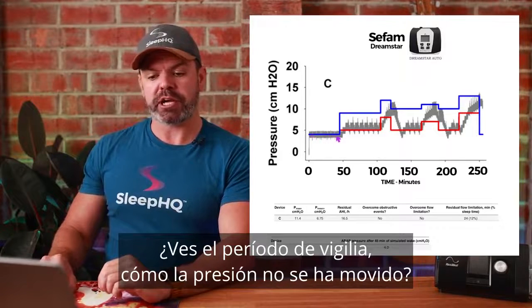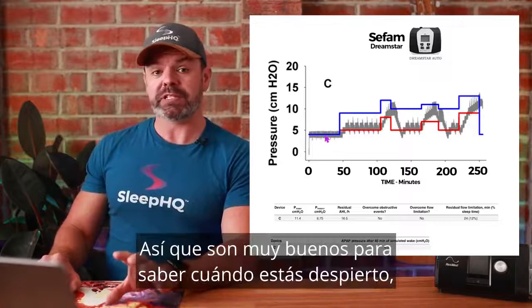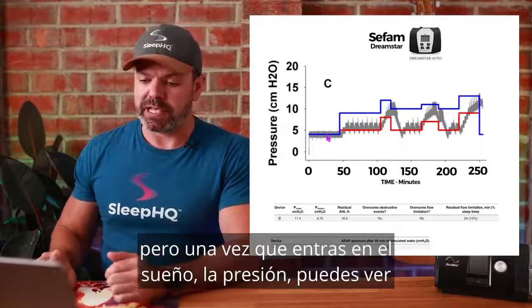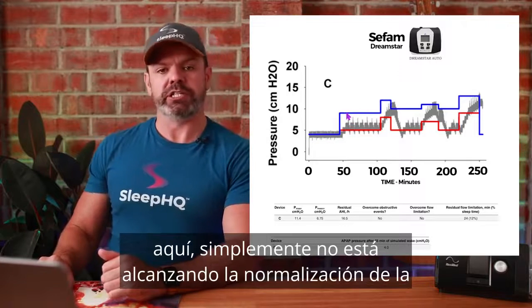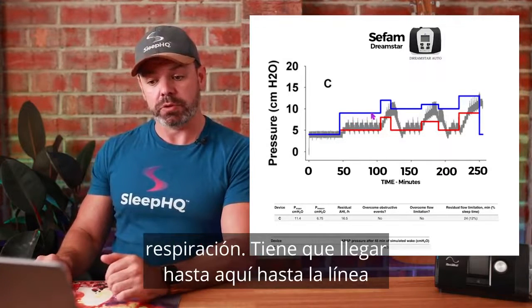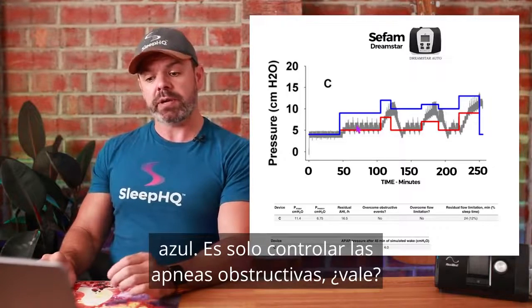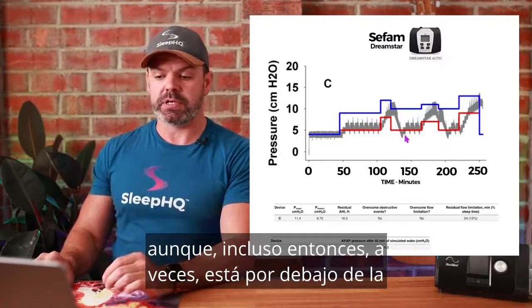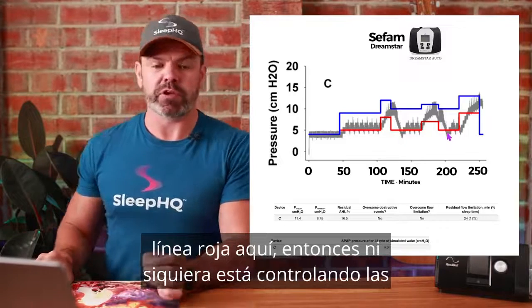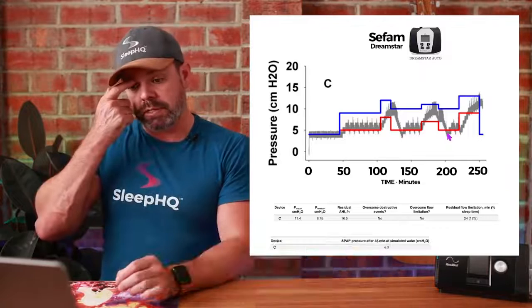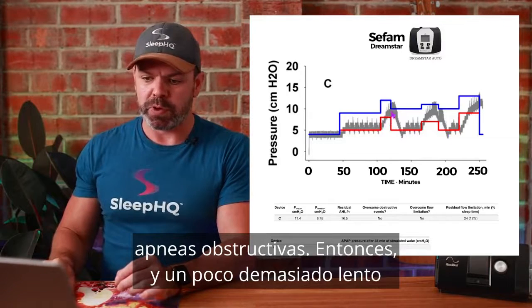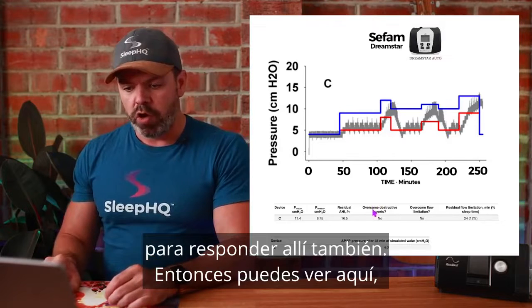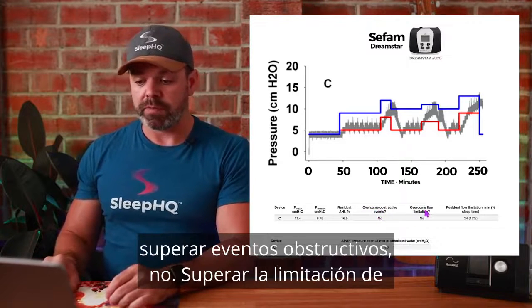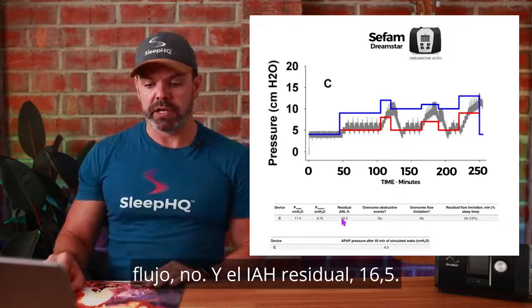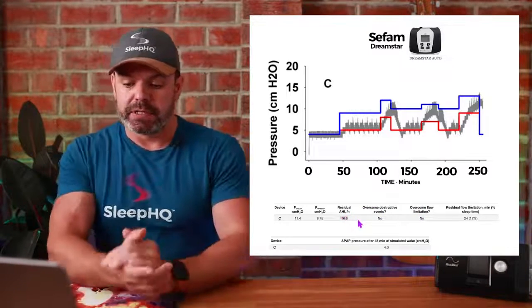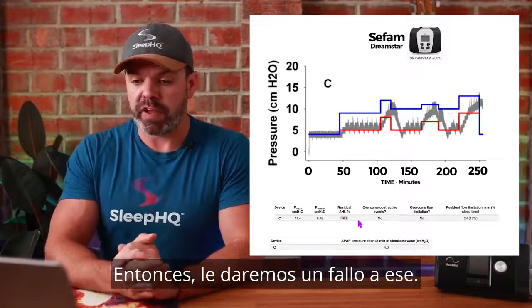See the wake period, how the pressure hasn't moved. So they're very good at telling when you're awake, but once you enter sleep, the pressure, you can see here, it's just not reaching breathing normalization. It's got to get up here to the blue line. It's just controlling the obstructive apneas okay, although even then sometimes it's below the red line here, so it's not even controlling the obstructive apneas. And a bit too slow to respond there as well. So you can see here, overcome obstructive events, no. Overcome flow limitation, no. And the residual AHI, 16.5. So we'll give that one a fail.